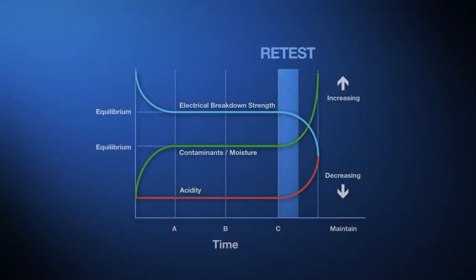The next criteria that we may find is a retest. In this case, the oil is indicating some degradation but not yet enough to warrant maintenance, and in this case we would retest in two to two and a half years.